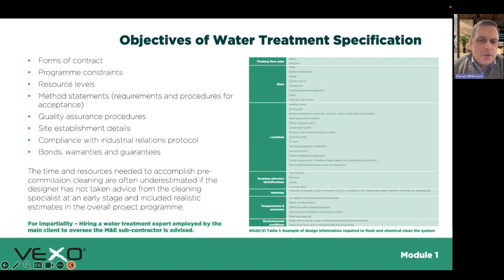There's a lot of good information in the BSRIA guide in terms of forms of contract, method statements, and considerations around quality assurance, making sure there's plenty of due diligence prior to the project starting. It's always good to involve a water treatment specialist at the design stage, because they can advise on the design in terms of allowances for getting the system clean. Without that, it becomes very challenging once the system's handed over, if you haven't fully cleaned and removed foreign objects, construction deposits, or corrosion.